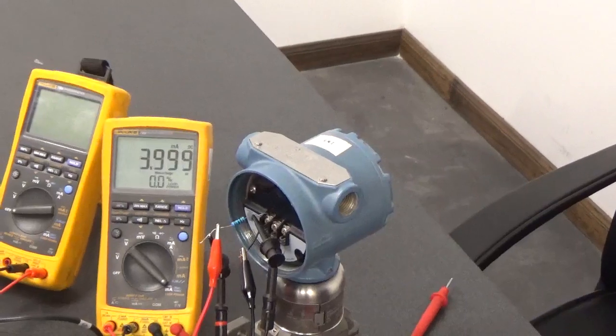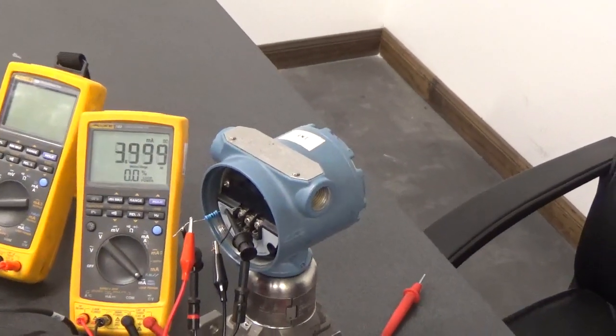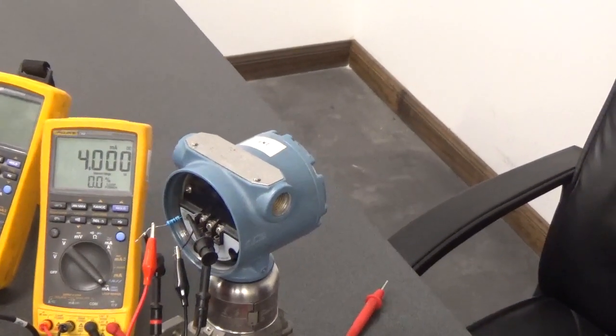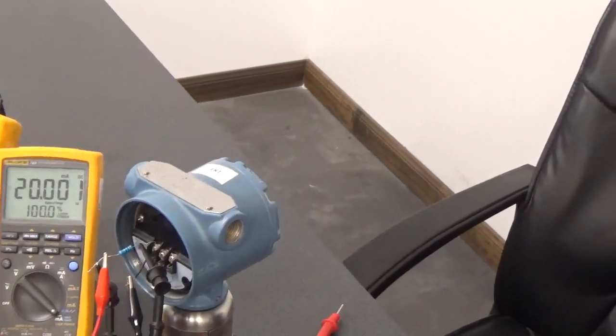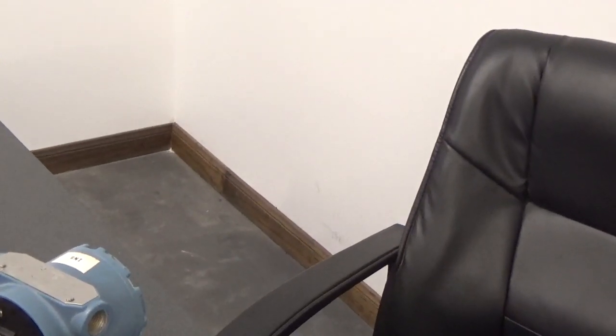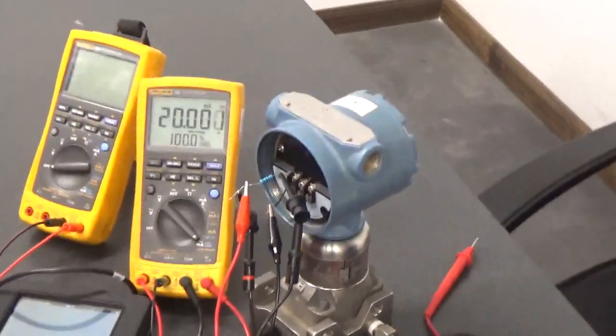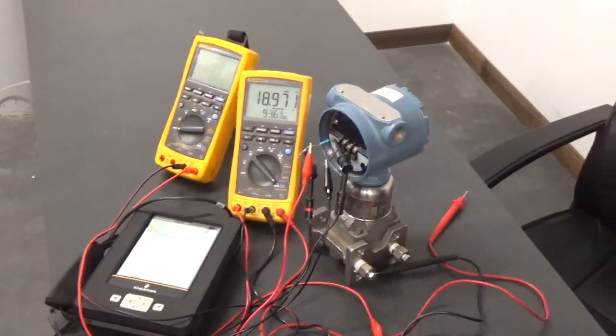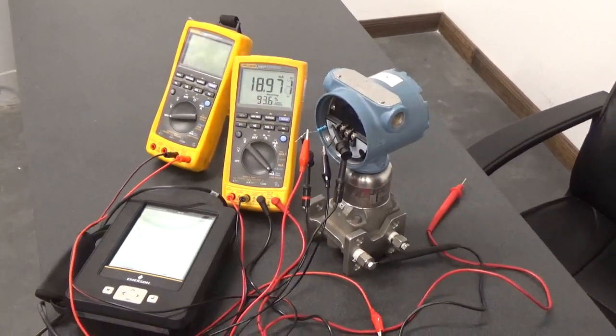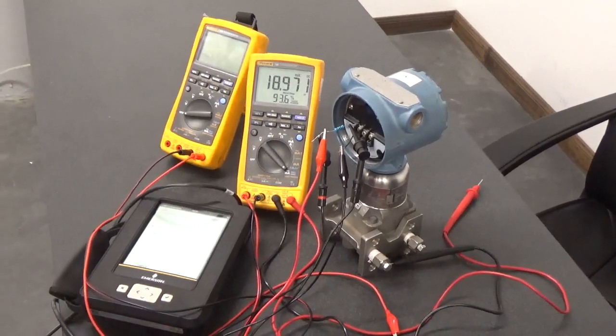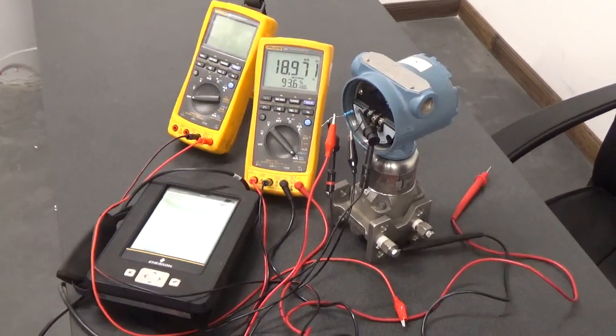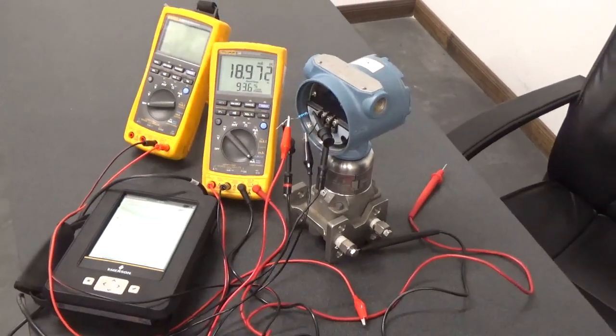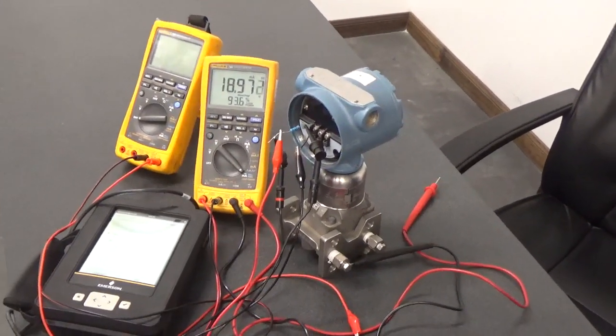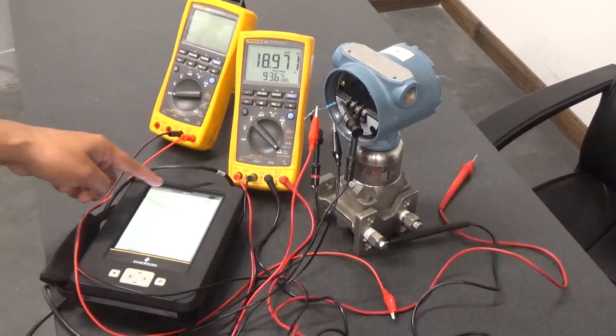You ready to do the upper range? 20 milliamps. Okay. Now put 21.1. And look what happens to the signal. You see that? That's a bad milliamp signal. But yet, the device is telling this communicator that I'm putting out 20 milliamps. Yeah. Now fix it, Raul.